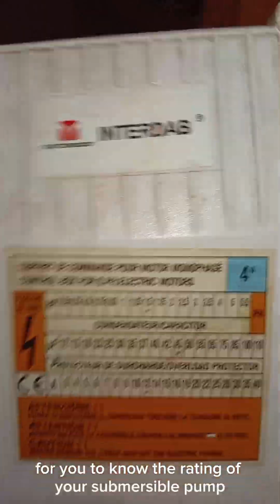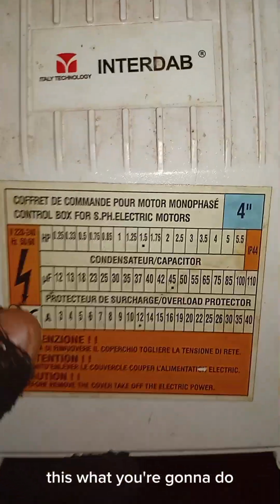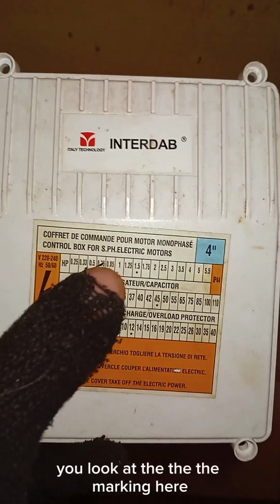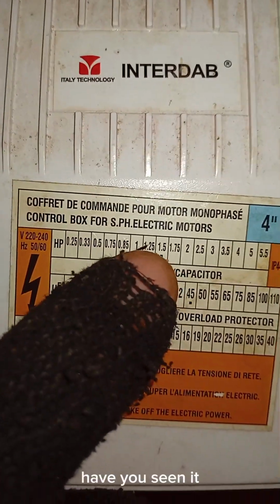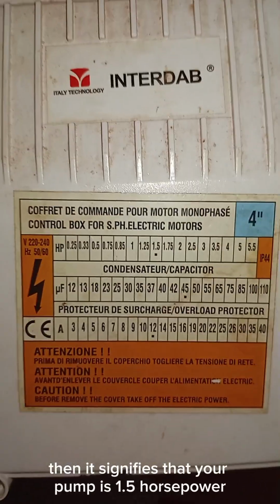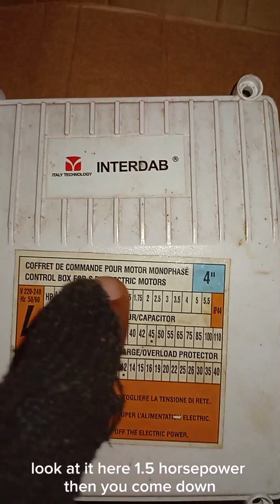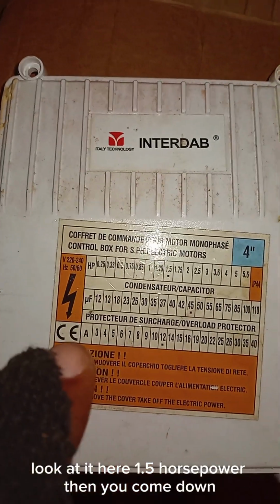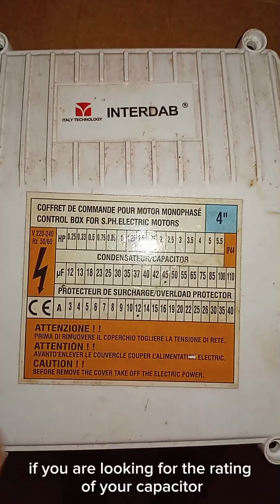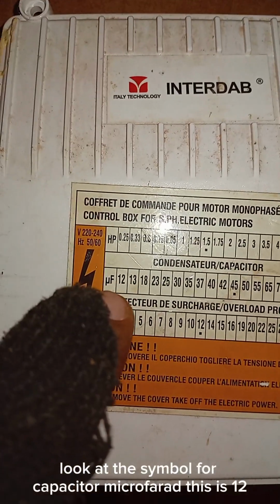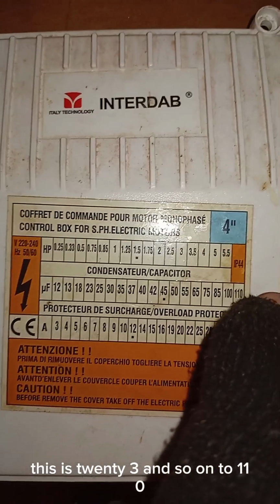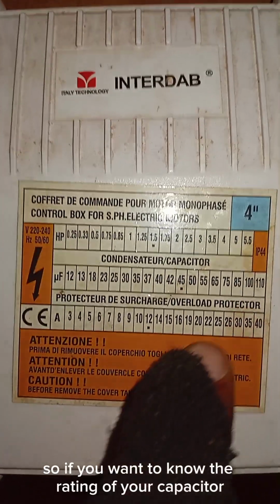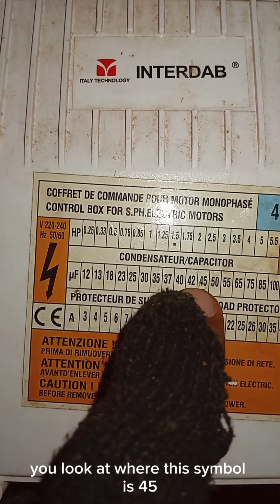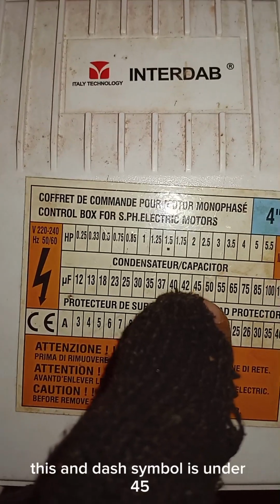So for you to know the rating of your submersible pump, this is what you are going to do. You look at the marking here. There's a mark here. Have you seen it? Then it signifies that your pump is 1.5 horsepower. Look at it here, 1.5 horsepower. Then you come down. If you are looking for the rating of your capacitor, you look at the symbol for capacitor, microfarad. This is 12, this is 13, this is 18, this is 23, and so on till 110. So if you want to know the rating of your capacitor, you look at where this symbol is, 45. This dash symbol is under 45. So you come down.